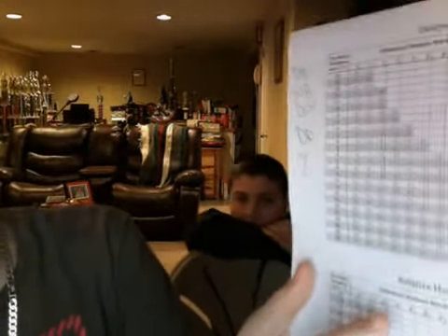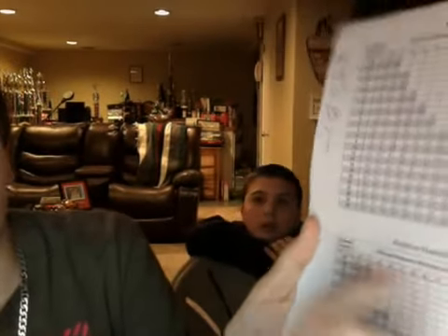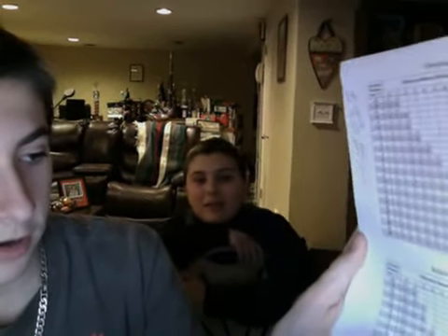John here will tell you how you find the relative humidity. To find the relative humidity, you know how the dew point is right here? You go down a little bit, and there's the relative humidity. For the relative humidity, you find the difference between the dry bulb and the wet bulb, like in the dew point, and then you find the dry bulb temperature, which is right here. For instance, let's say the difference was 1 degree. Then you would go down to the dry bulb temperature, which is, for instance, 4 degrees outside. You would go down to the 1, down to the 4, and you'd have a relative humidity of 85%.